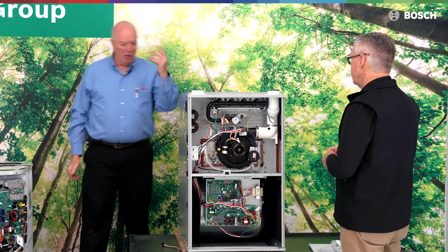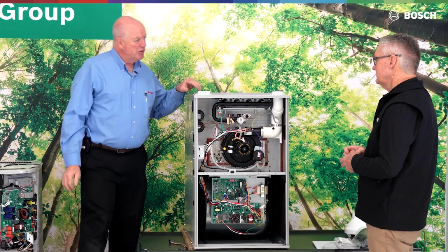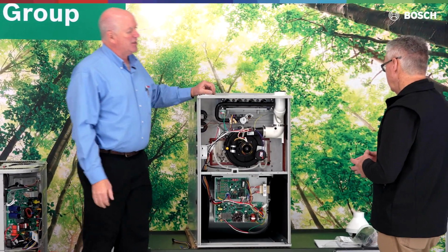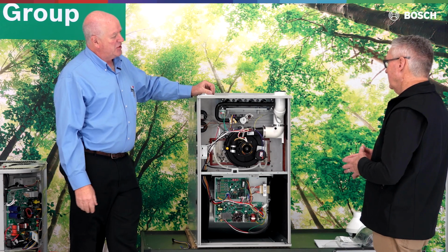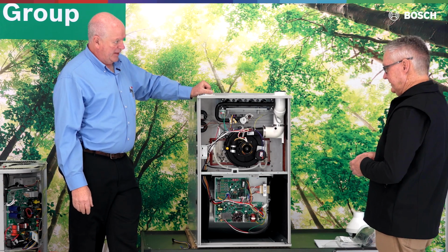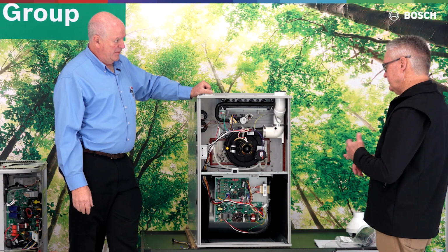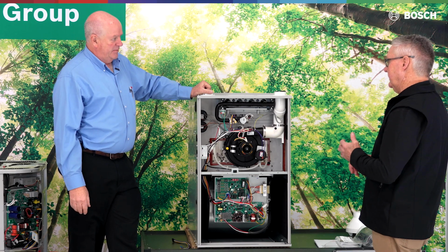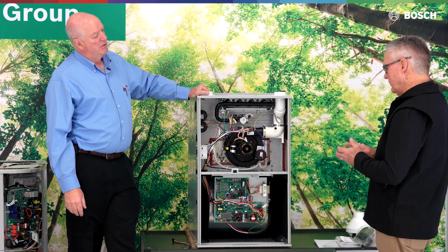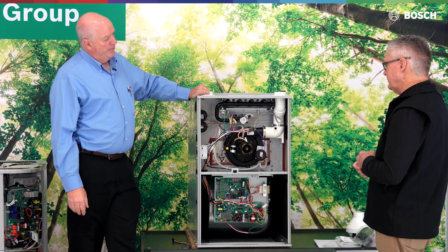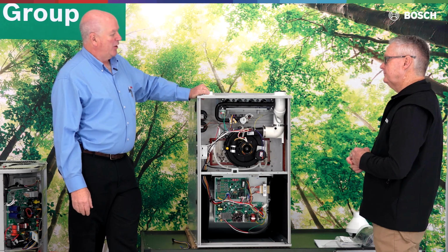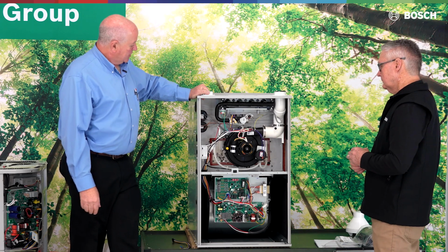So what if you're over a 60 degree rise? What would you suggest someone do if they're over 60, say a 90 degree rise across this unit? You probably need to look at your static to make sure your airflow is correct, and increase the airflow. You might also want to take a look at your gas pressure and drop it back a little bit if you have to. That's an awesome feature.